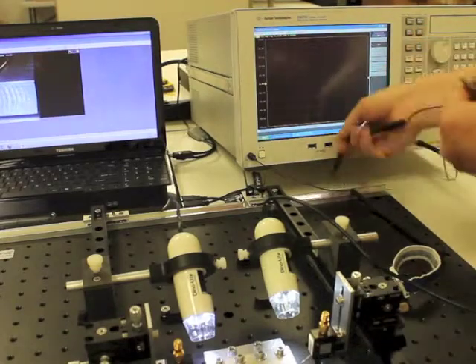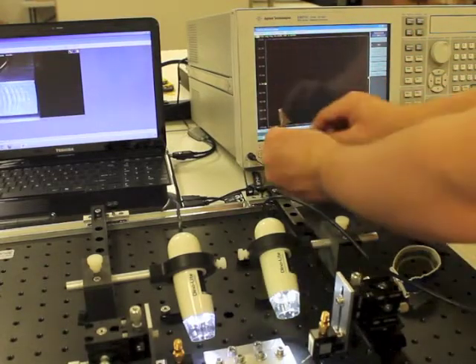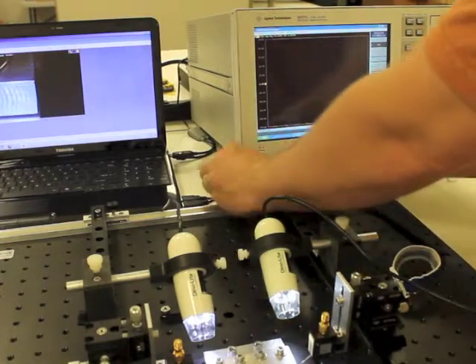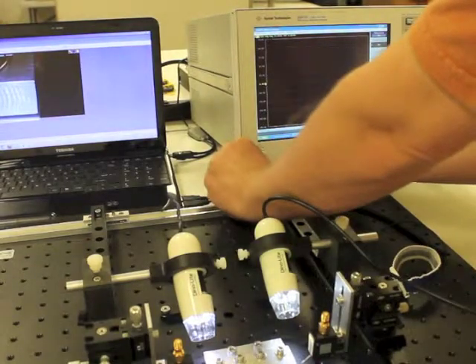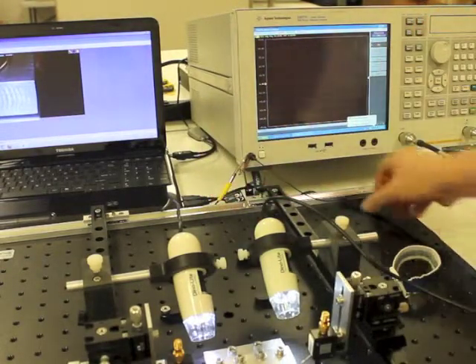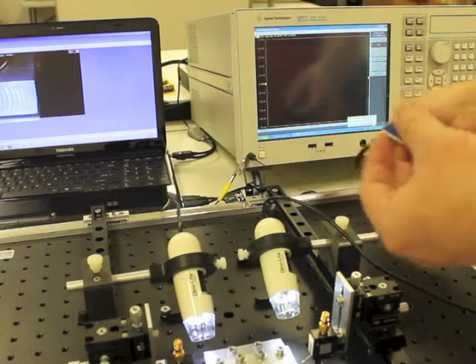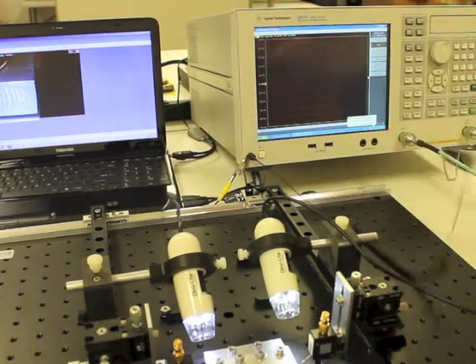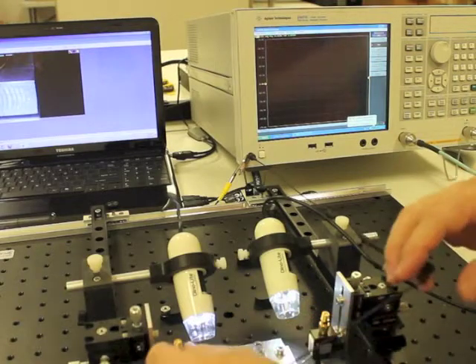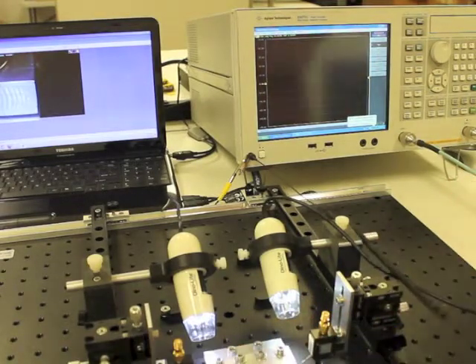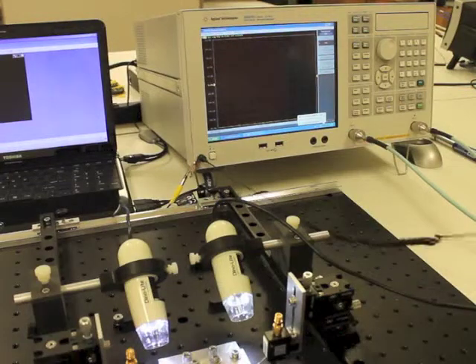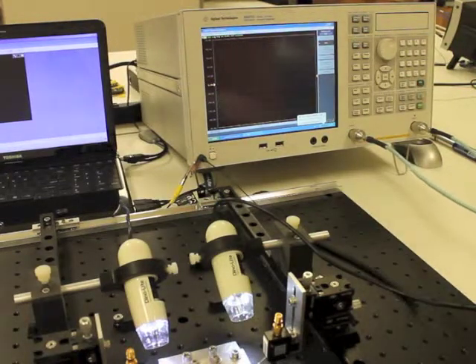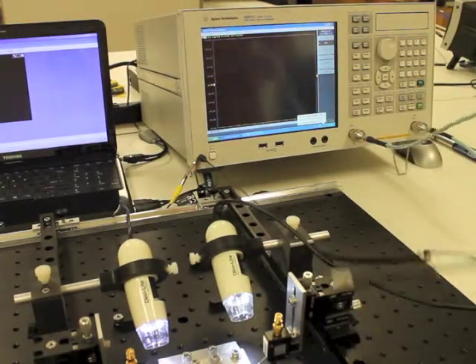Once the sample has been placed in the fixture, we are now ready to do a measurement. First thing we do is ground the probe station. This should be grounded at the probing point of the instrument that you're going to use, and you should wear a grounding strap on your wrist. This is connected to an Agilent vector network analyzer, the E5071C. Notice that I also touched the ground connections of the probes to discharge them through my body.